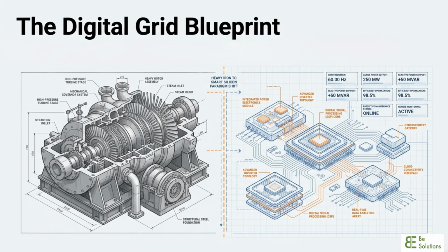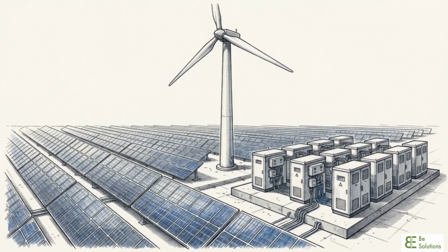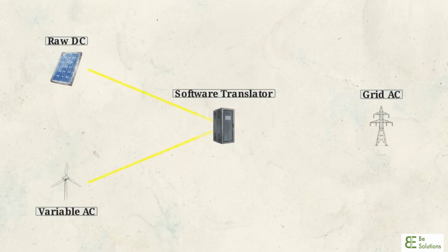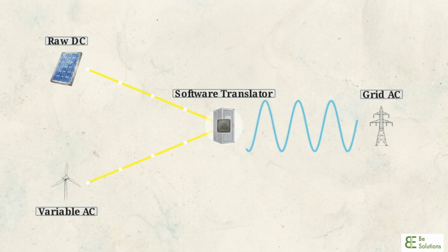If an asset doesn't directly turn a physical rotor to interface with the grid, it's an inverter-based resource, or IBR. Utility-scale solar, wind turbines, and battery energy storage systems all fall into this category. Their connection to the wider power network relies entirely on software algorithms, translating their energy into grid-compatible AC power.